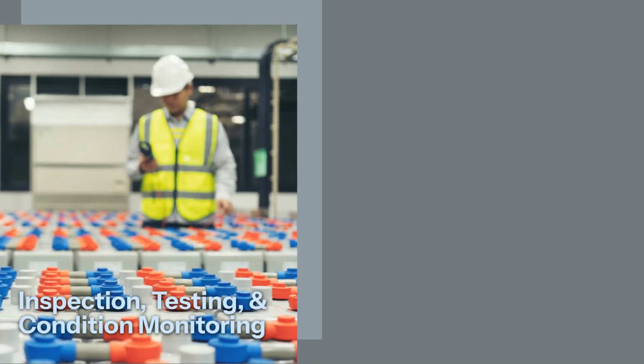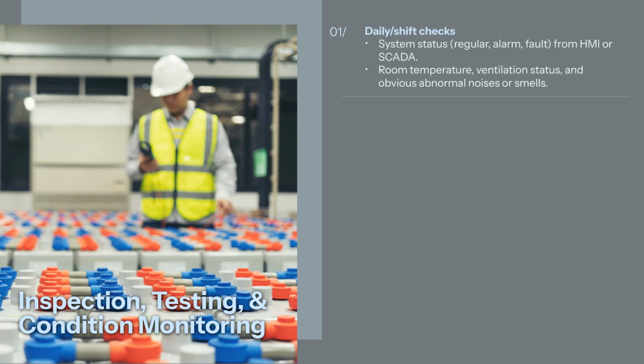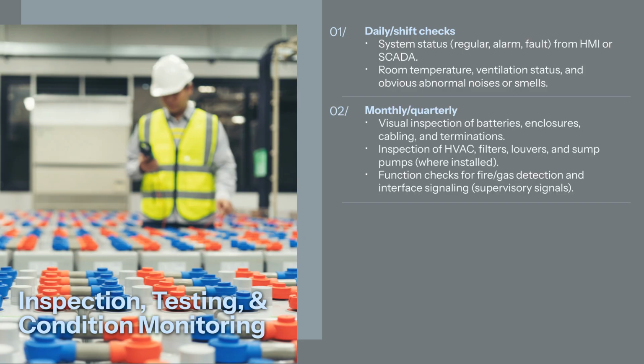The next area that we will look at is inspection, testing, and condition monitoring. We will look at routine inspections across technologies. Typical battery energy storage system inspection layers will include daily shift checks: system status, regular alarm or fault status from the human-machine interface (HMI) or supervisory control and data acquisition (SCADA), and room temperature, ventilation status, and obvious abnormal noises or smells. Monthly and quarterly checks will include visual inspection of batteries, enclosures, cabling, and terminations.